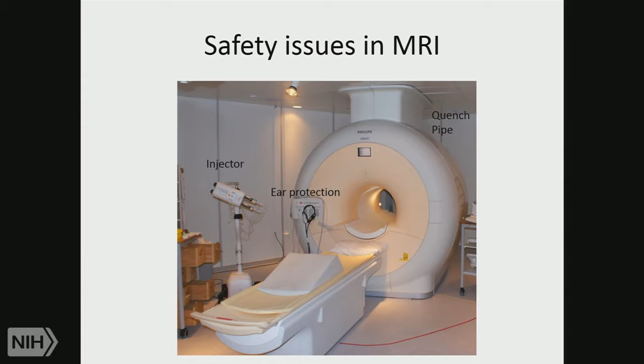Well, it burns, it creates heat, it vaporizes the liquid helium that's surrounding it, and all of a sudden you have this release of a tremendous amount of liquid helium being converted to gaseous helium. And you've got to get rid of that quickly, otherwise your room will fill up with helium and not oxygen or air. That means people in the room will suffocate. And I'm not kidding. That can happen. So what we do in every installation is have an emergency quench pipe that goes to the outside. It's designed to take the gaseous helium and vent it outside very rapidly so it doesn't accumulate in the room.